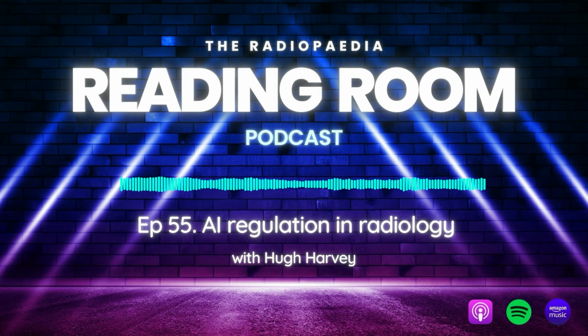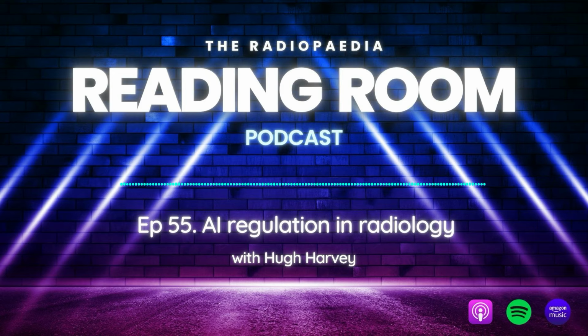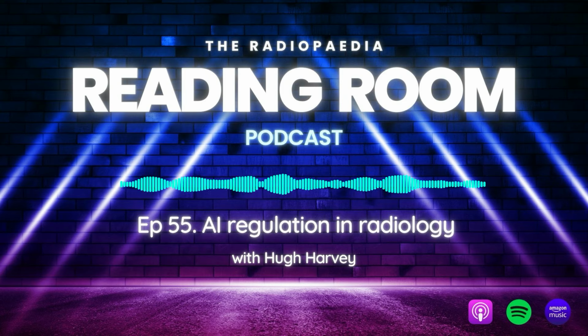So what are the key takeaways from today's talk? Intended use, and on the back of that, strong scientific and clinical evidence. Regulators want to see just as much clinical evidence as clinical buyers and commissioners. And although you're not mandated to publish the clinical evidence that you generate to get your regulatory approval, it's always recommended for transparency. Regulation doesn't just encompass patient safety and device efficacy, it also covers cybersecurity. That's super important to remember. And meeting regulatory and clinical standards also aligns with delivering really solid patient level and population level value.